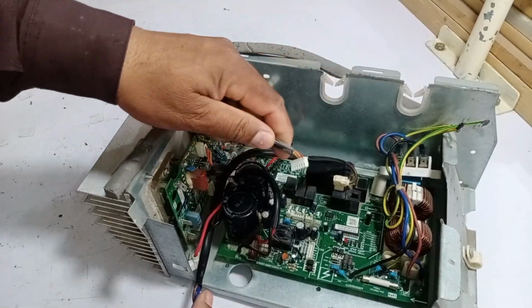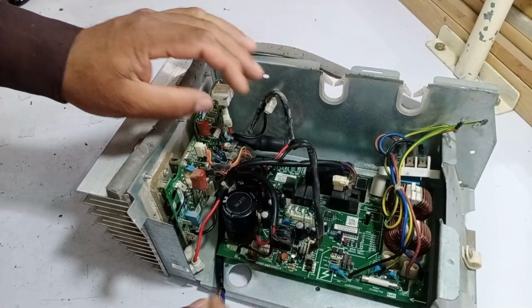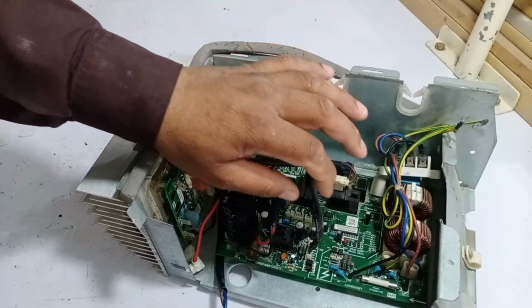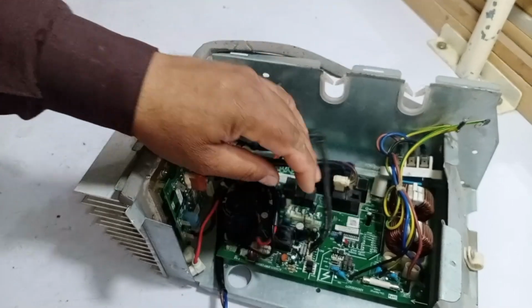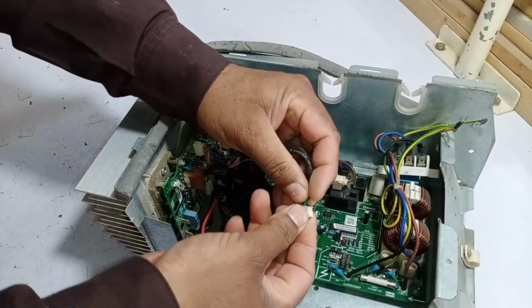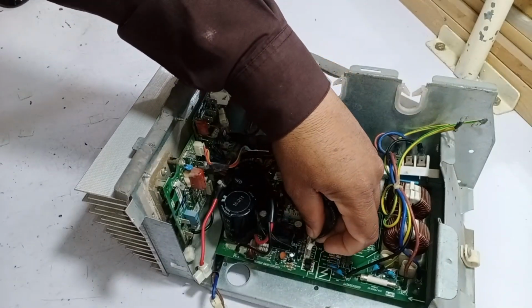What you should do is remove the connector because sometimes, due to vibrations from the unit, the wires can become loose. Additionally, rust can accumulate on the connector pins, which can disrupt the electrical connection. A good practice is to remove the connector, clean the wires, and slightly move them back and forth before reconnecting it. This ensures a firm and proper connection.